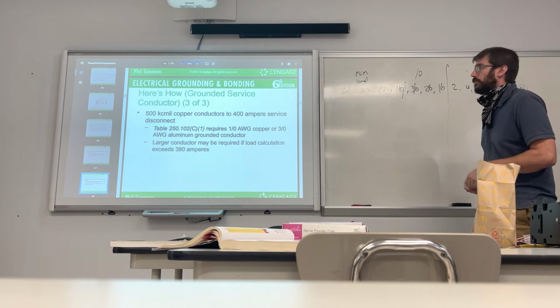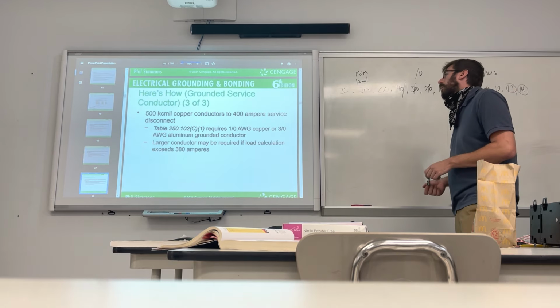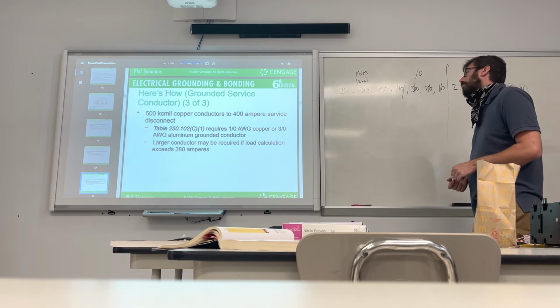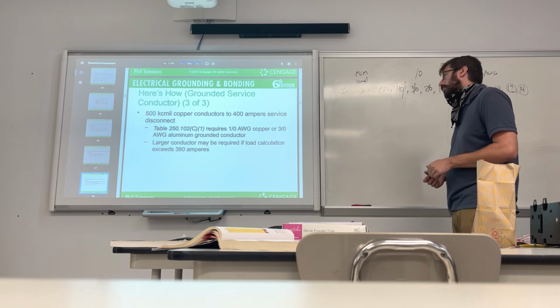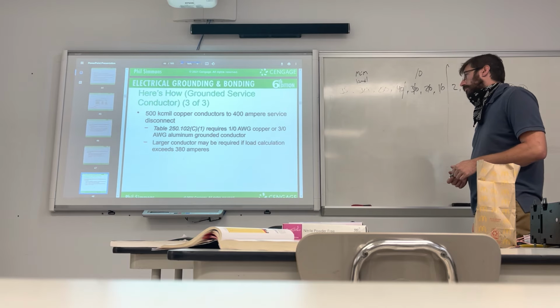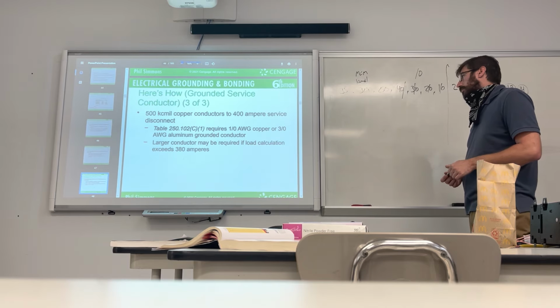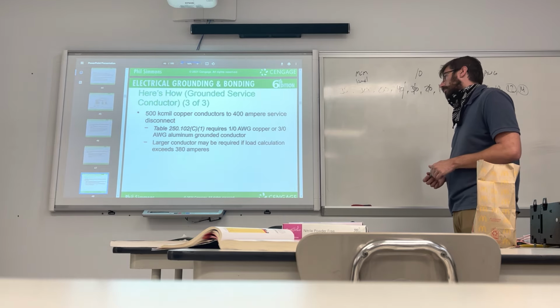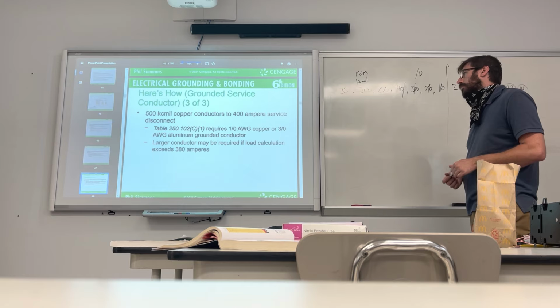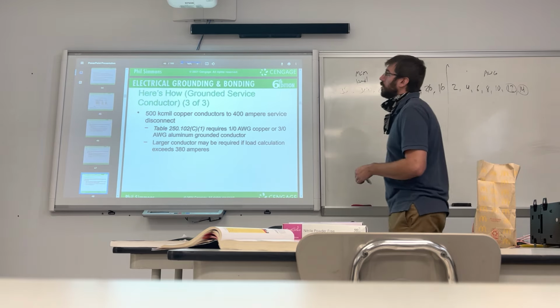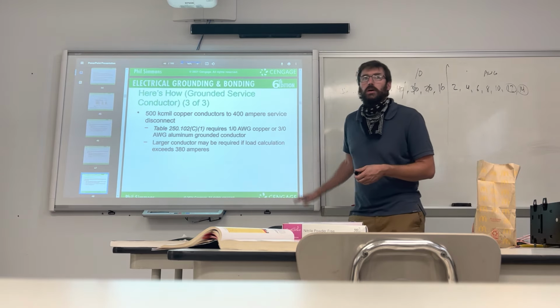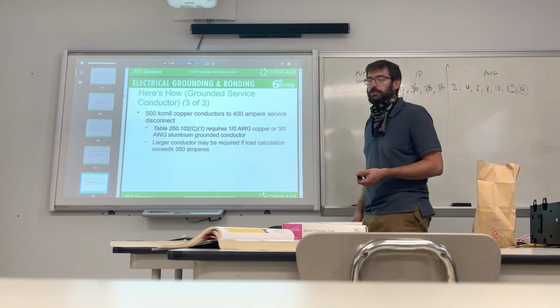What's the last one? Yeah. 500 kcmil copper conductors to a 400 ampere service disconnect. NEC requires 1-aught AWG copper, 3-aught AWG aluminum grounded conductor. Larger conductor may be required if load calculation exceeds 300 amperes or 380 amperes. But do we see with those three slides how this works? How it's not the most complicated thing in the world? It just goes by the service power coming in.